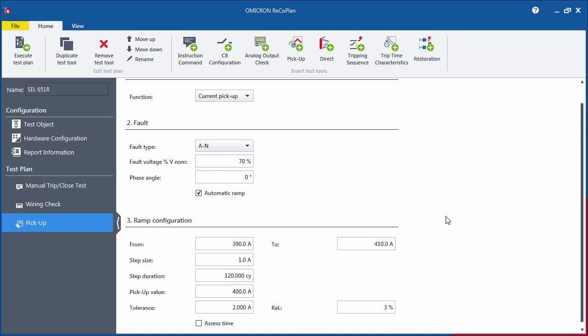You also have the option of using automatic ramp. Then, you can define the start and end points of the ramp, as well as the step size and duration. Also enter the pickup value and the current tolerances.